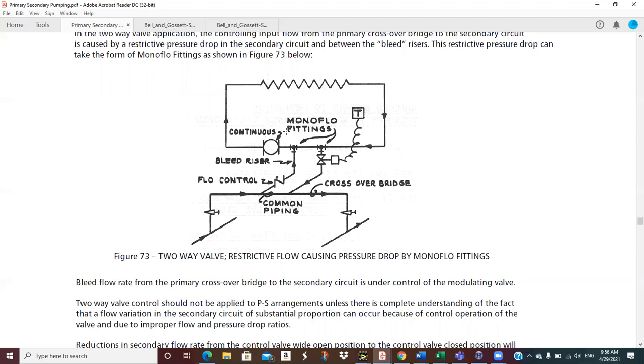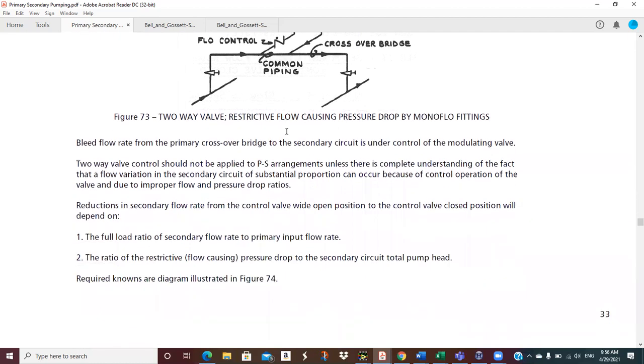Okay, let's see, bleed flow rate, that's up from the crossover into the secondary, is under control of the two-way modulating valve. Two-way valve control should not be applied to primary secondary arrangements unless there is a complete understanding on the part of the engineer of the fact that a flow variation in the secondary circuit of substantial proportion can occur because of the operation of the valve due to improper flow and pressure ratios.